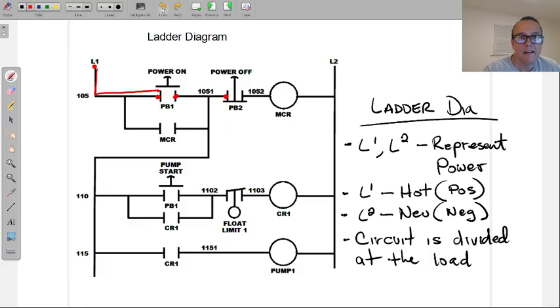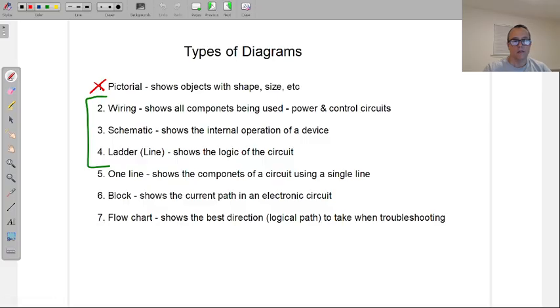However, as I said, that's on paper. Now find the float switch, find the pump, find these wires, troubleshoot the wires. So there's the hard part. Ladder diagram helps us the most, going back over to the list of those three - in my opinion, schematics are a little bit out of the window for motor control, it's more so for machinery. But between wiring and ladder, ladder is the choice.